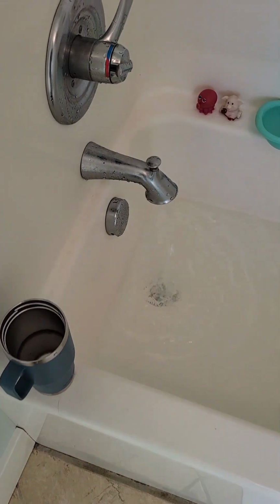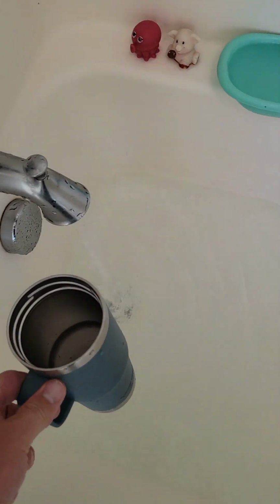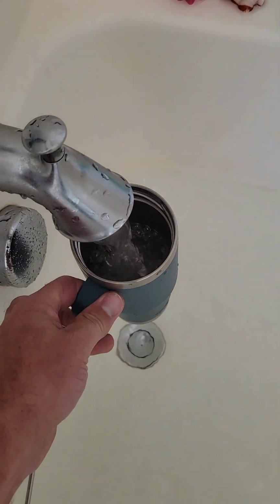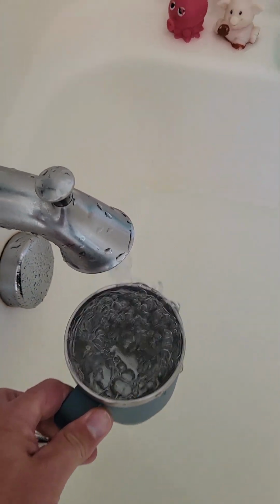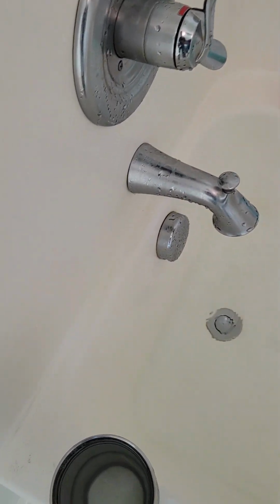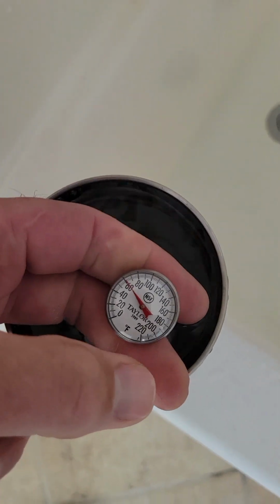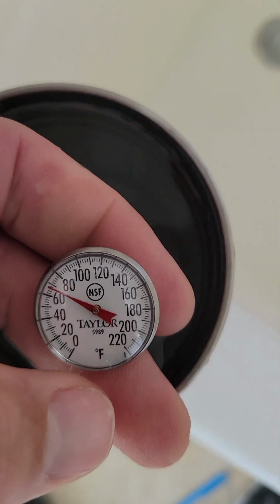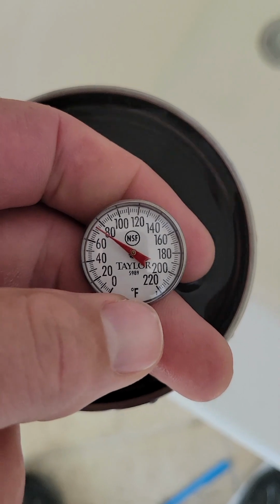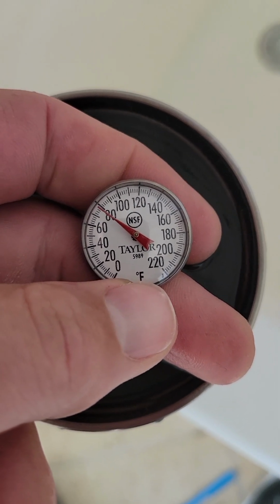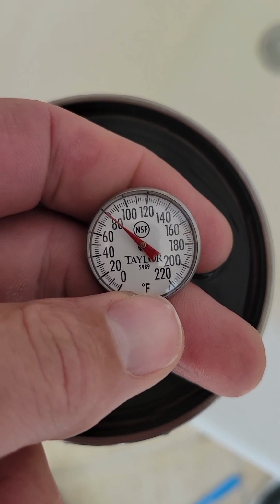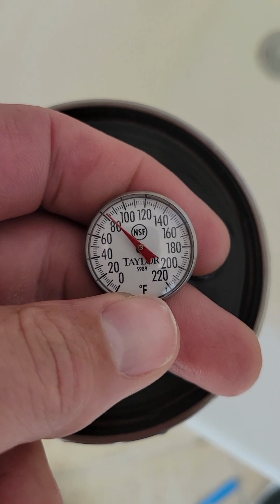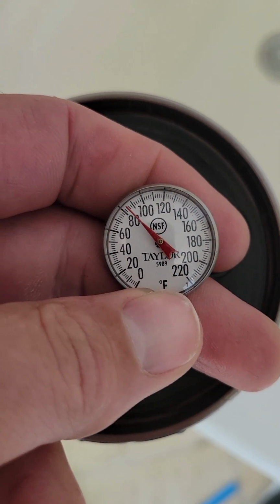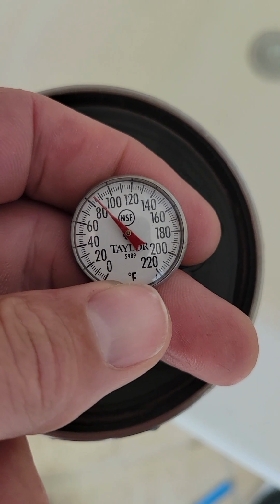All right, I think we've run it a few minutes now - should be a good time to take another sample. Here is the moment of truth. If it gets to 90 and stops, that's where it was the first time, and that would show we made a 5-degree difference with a 48-inch Graywater heat exchanger.